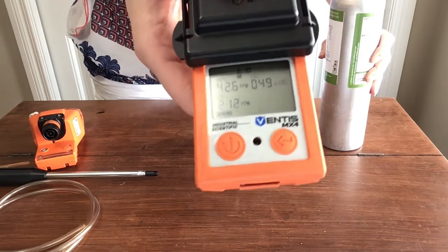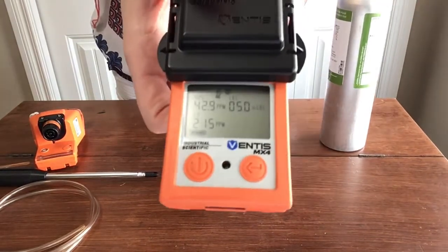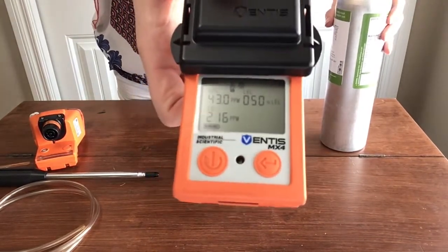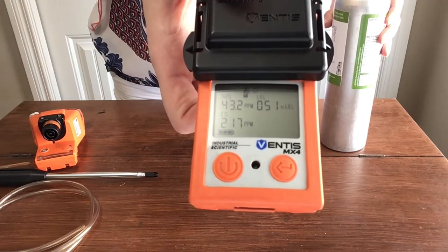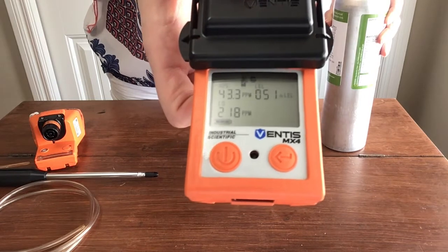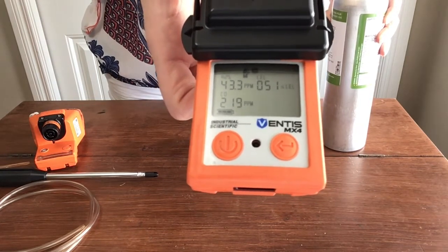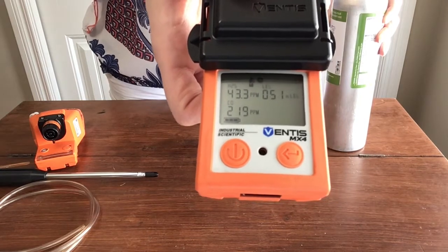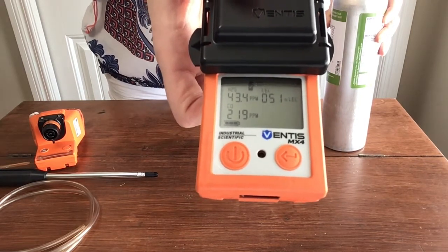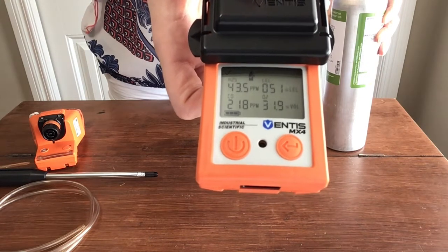Okay, and you can notice your little clock flashing on the top here, and that lets you know that it's going through its calibration. And again, you're not done here until you get P's or passes on all of these, and you see the lights flash, you hear it beep, and you feel the vibration. So you also need to make sure that all the alarms are working. Okay, so everything's passed.